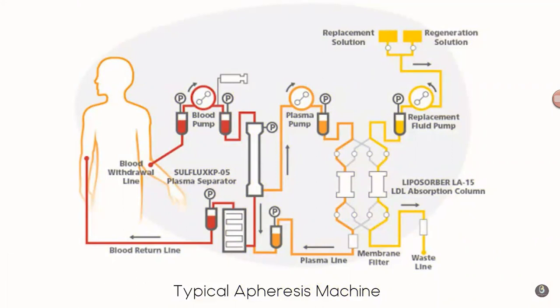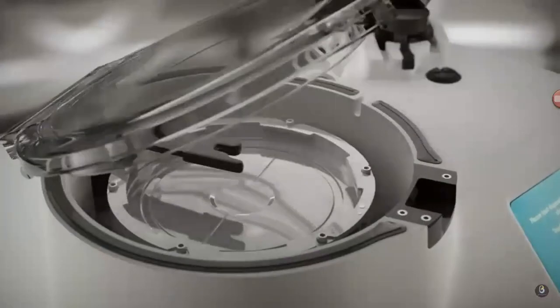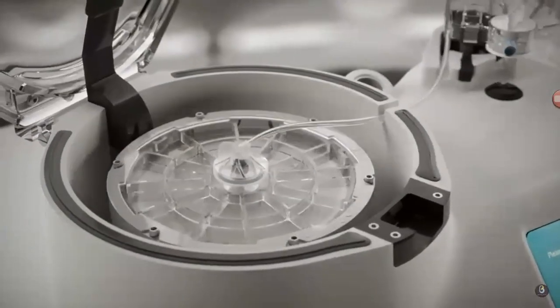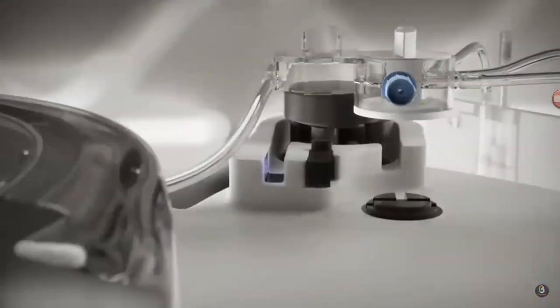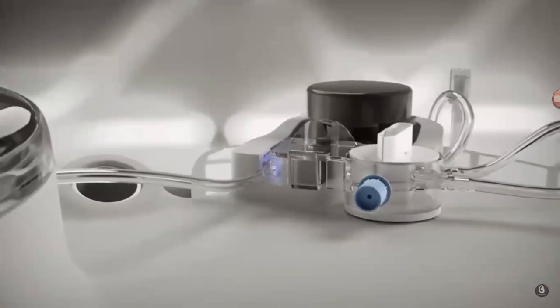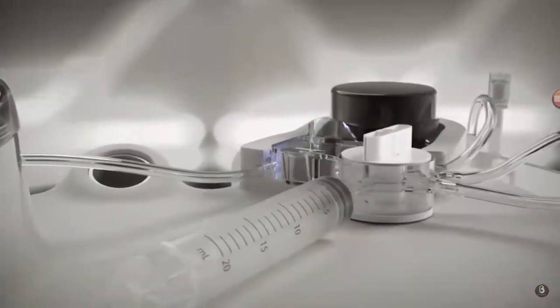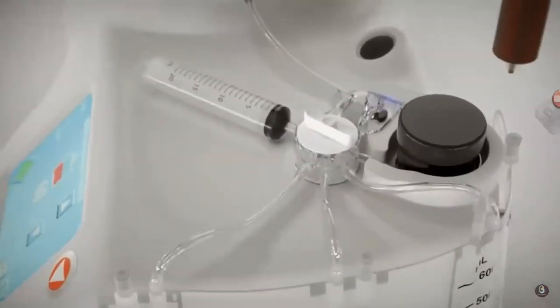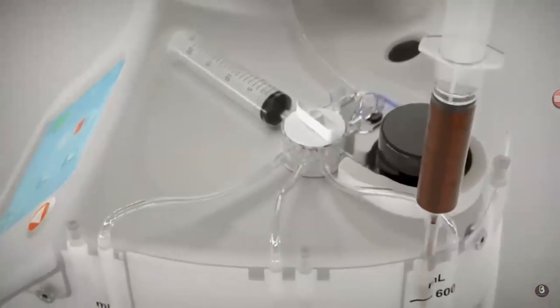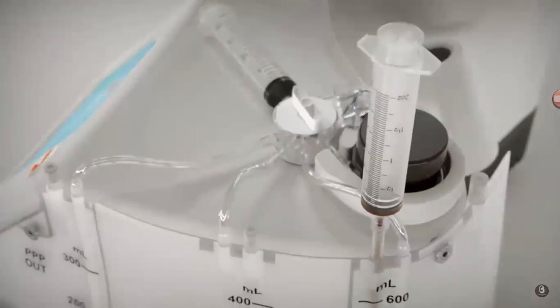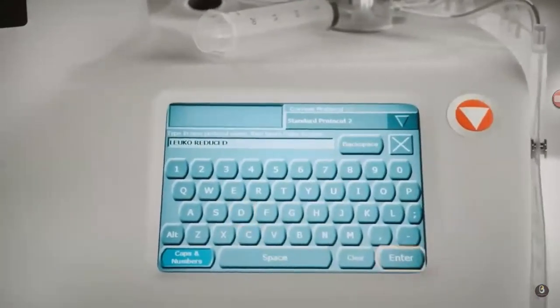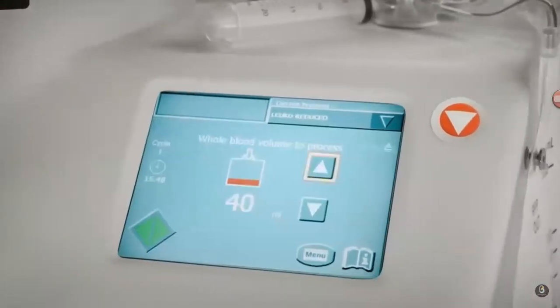The operator programs the unit to run the desired separation protocol. The unit automatically controls the centrifuge, pump, and other settings. Rotary peristaltic pumps draw blood from the patient or donor and pump blood through filters or centrifuges. Filters separate blood components based on size, centrifuges separate by density. Optical sensors detect plasma cell interfaces to minimize contamination from other components. Centrifuges have inlet and outlet ports and compartments to keep components separated. Pumps move the blood products into collection bags, add anticoagulant, and reinfuse fluids. Replacement fluids, e.g. saline, serum albumin, plasma protein fraction, fresh frozen plasma, are infused into the patient to maintain appropriate intravascular volume and pressure. Let's end this video with the operating steps of an apheresis machine.